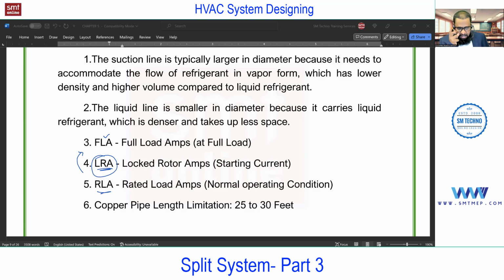In some cases, RLA and FLA are going to be the same if the compressor has a fixed speed. But now we have inverter and variable speed compressors also. In that case, FLA and RLA are going to be different. In a same-speed compressor, FLA and RLA we can consider the same. And LRA is common for all types because that's the starting current. And these may be asked in interviews, very common terms.